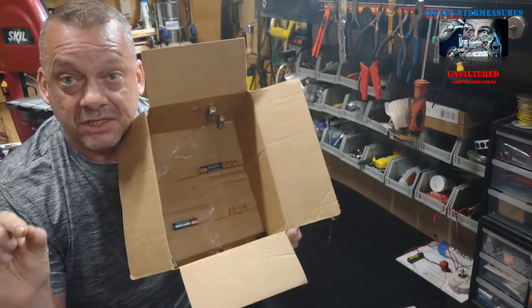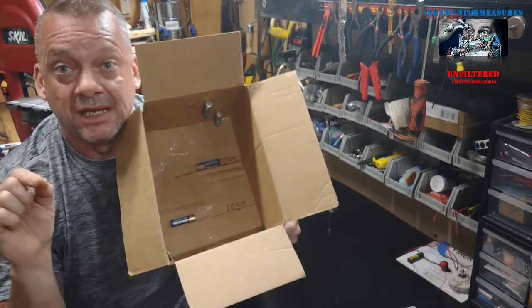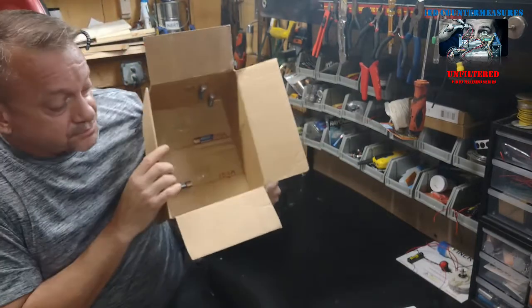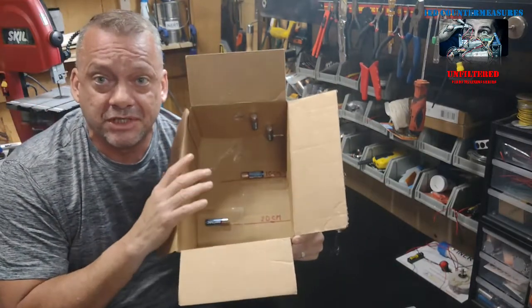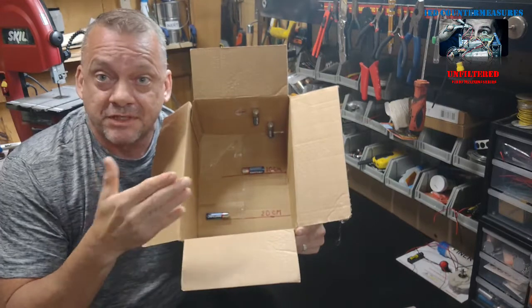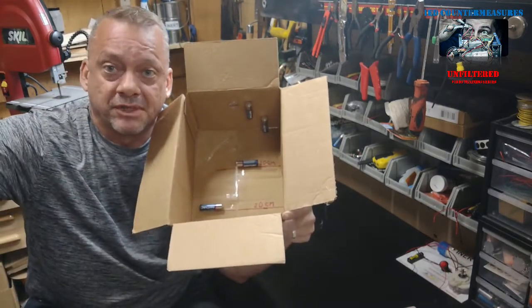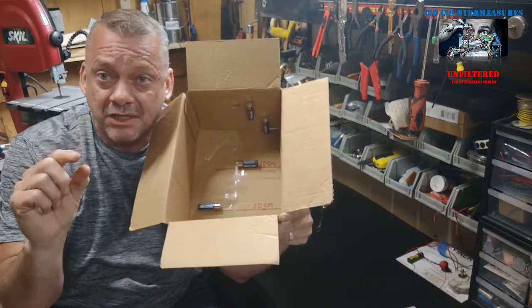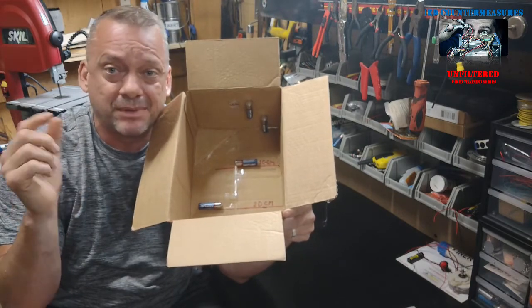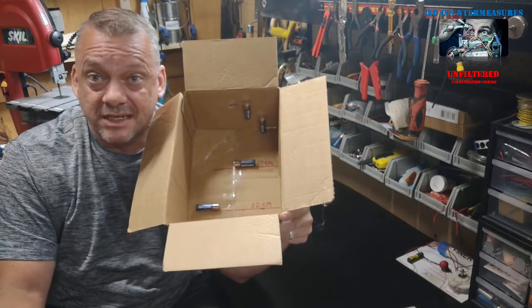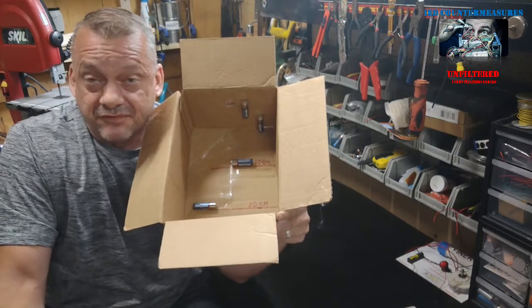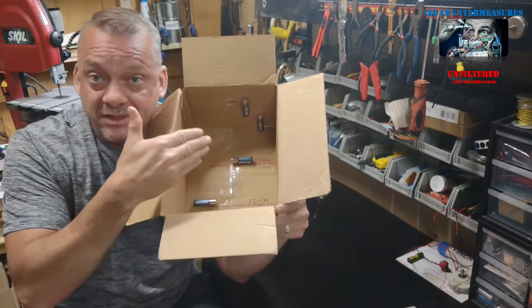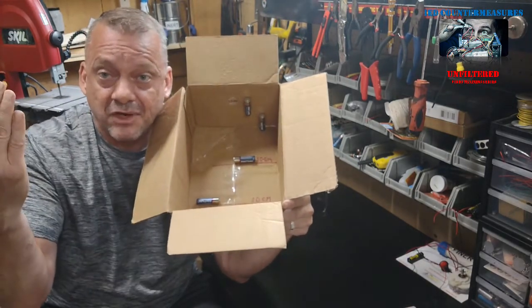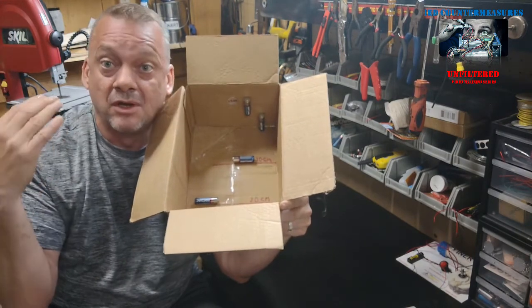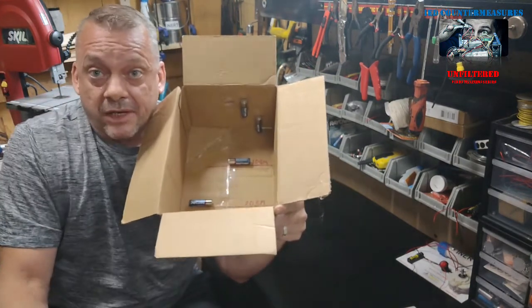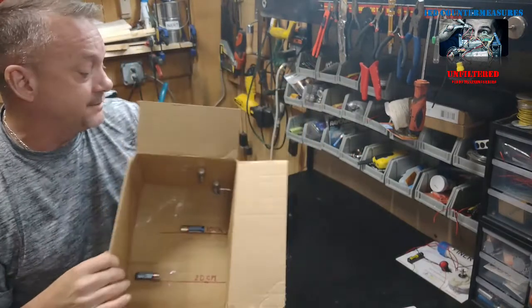So again, it's a combination of the panel's lower edge dead zone and the height of your X-ray generator. The next thing you want to do is when you get those measurements, back your generator up farther. You'll see a slight reduction in your lower edge cutoff, but it gets to a point where you won't see any more change. It is what it is, it's basic physics - you have a dead zone in your panel and a certain height of your generator's aperture off the ground, which correlates into a dead area. Plain and simple.